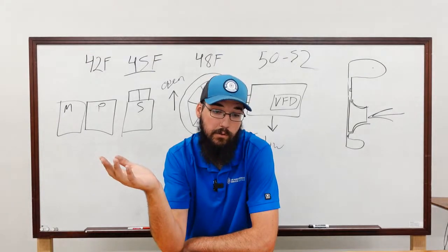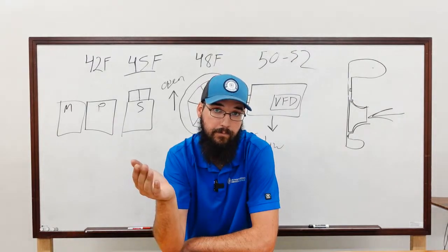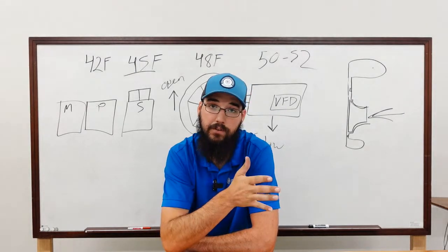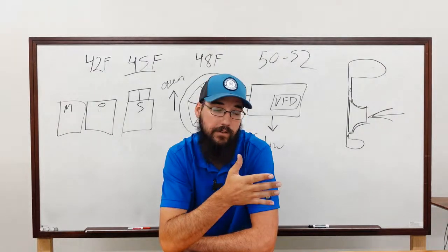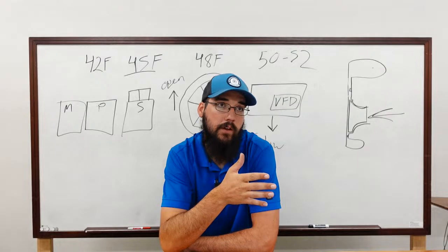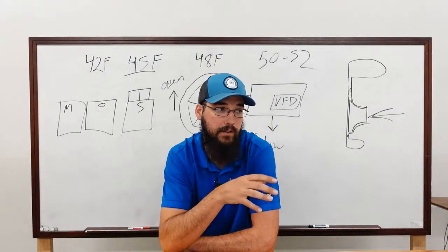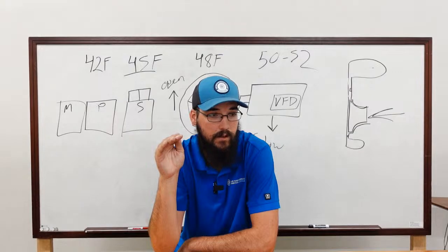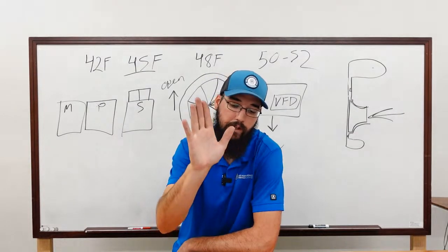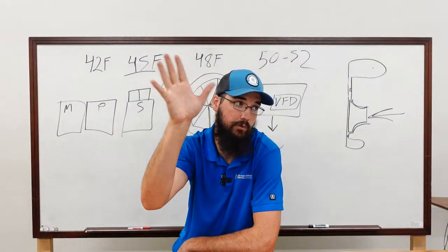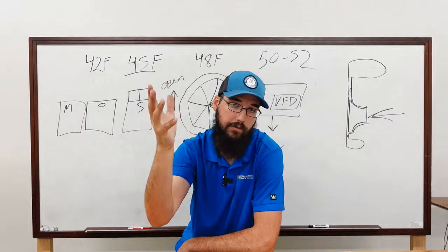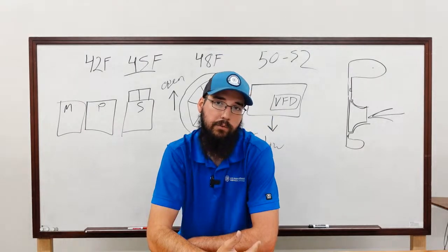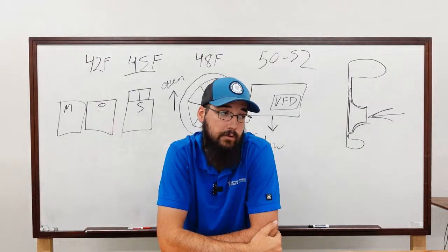So, all right, we're working on a machine that doesn't have a variable geometry diffuser, all right? The way that we can stop the surging is, one, closing the guide vanes. That is an immediate way, because the way closing the guide vanes helps is it lowers how much refrigerant is being pushed, and so it allows less refrigerant to stack in the diffuser and going into the volutes. So there's less molecules moving. And because of that, we're essentially removing the lift out of the equation, or reducing the lift down enough to where we're not going to stall at that point.